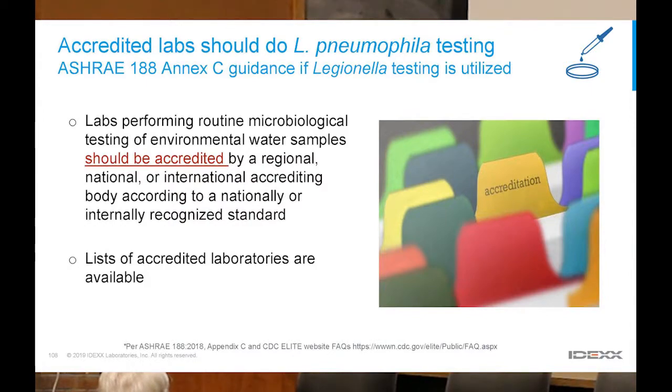Because when you have your validation testing done, you are going to get a result. Some number of Legionella pneumophila per 100 ml. That is your data that tells you if your plan is effective or not. So you want to make sure that whomever is going to be doing that testing knows what they're doing, because you're making decisions on that data. So my recommendation, and the recommendation within ASHRAE 188, is to use a laboratory that is accredited to a national or international standard, right? And in Canada, I believe that you ascribe mostly to ISO 17025 as the basis for your laboratory's accreditation, right? And there are lists from CALA and SCC. Those are two accreditation bodies in Canada that you can get lists of accredited laboratories in your region, okay?